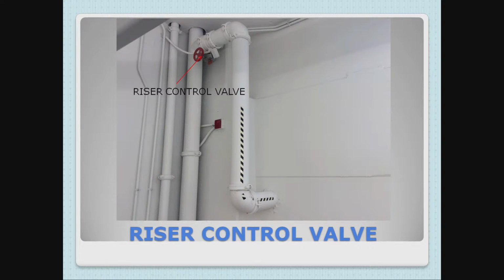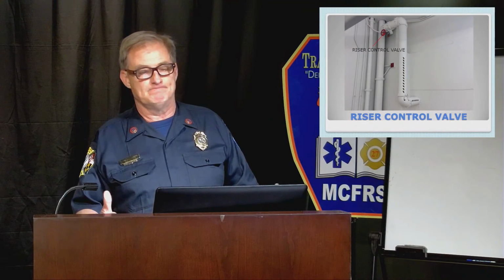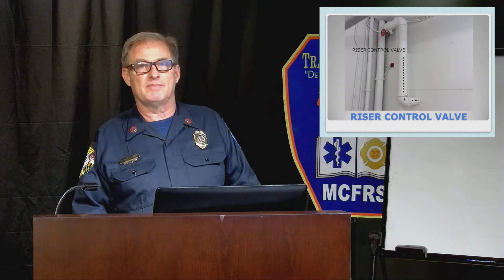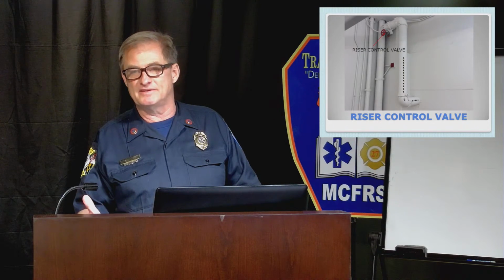Well, it had a pressure test put on it, and that's fine, but a pressure test doesn't replicate the dynamic forces of actually flowing a lot of water. And what happened was we had enough dynamic forces, and it was a double elbow. So picture 2 of these elbows kind of mated to each other to change in elevation. It was a double elbow, so your forces are going to kind of be multiplied as it goes through that double elbow, and it eventually gave up the ghost. So there's not a scenario I could come up with where the pumper operator made some mistake or something. It just wasn't the case. It was a fitting that sat for many years, and finally when it was called on to be used, it didn't work.